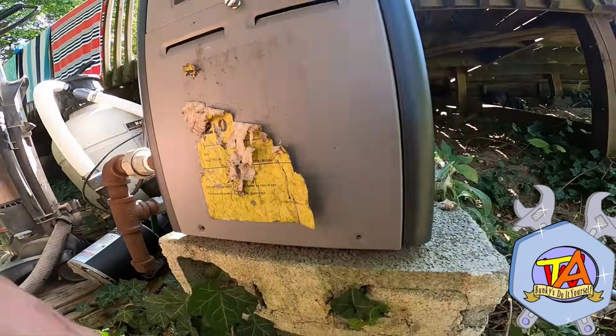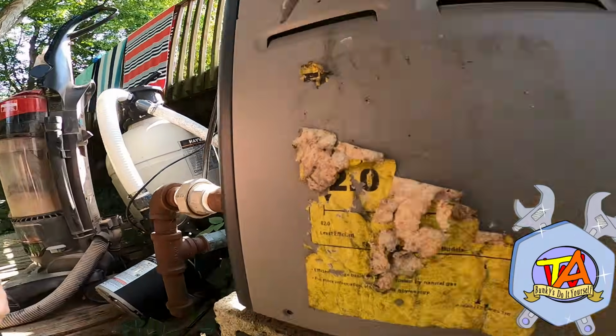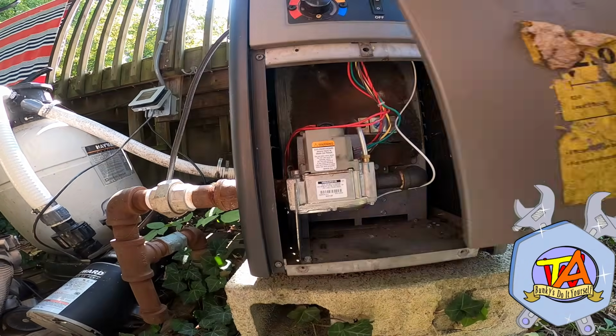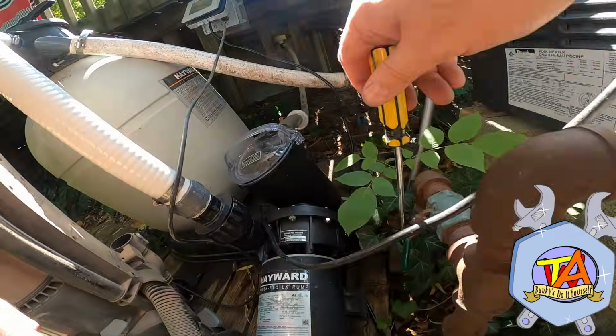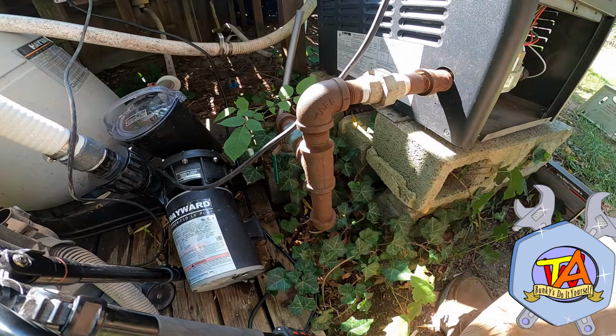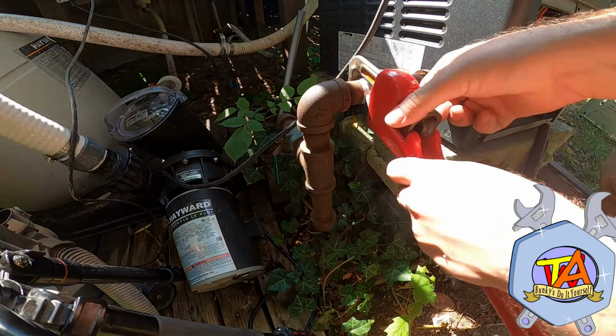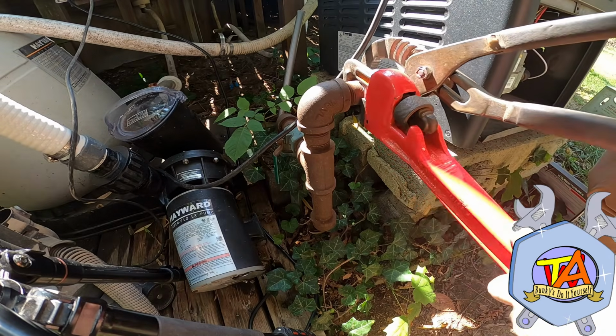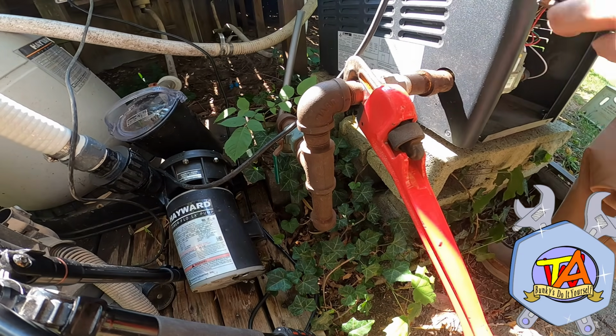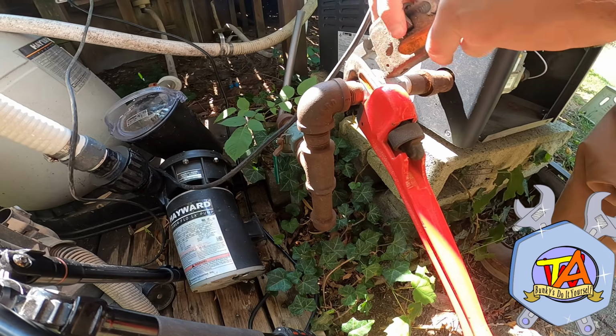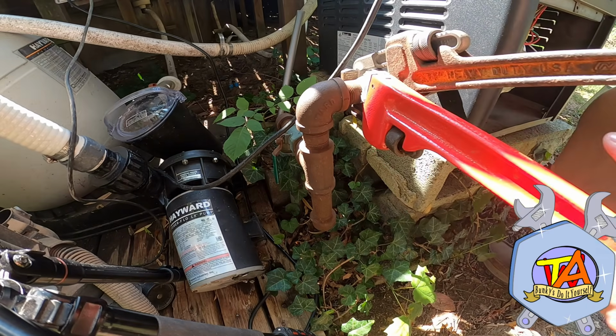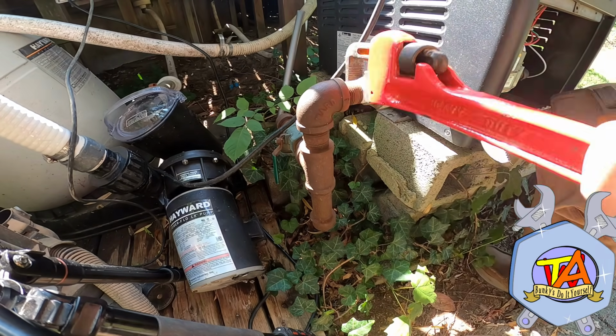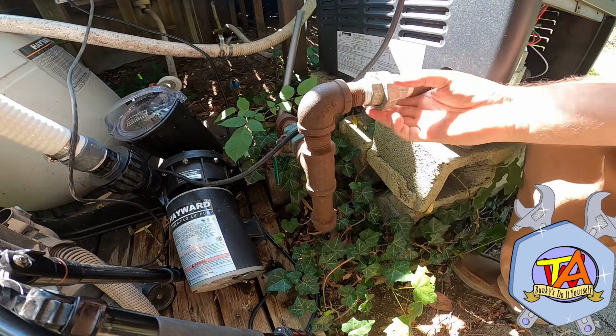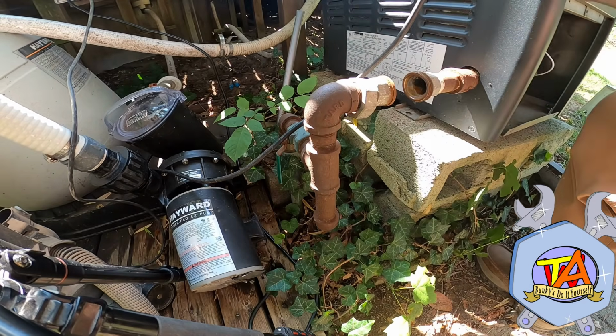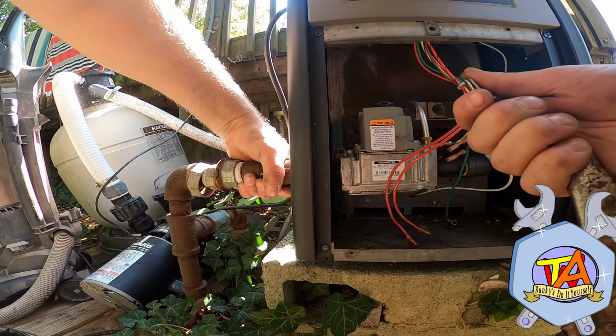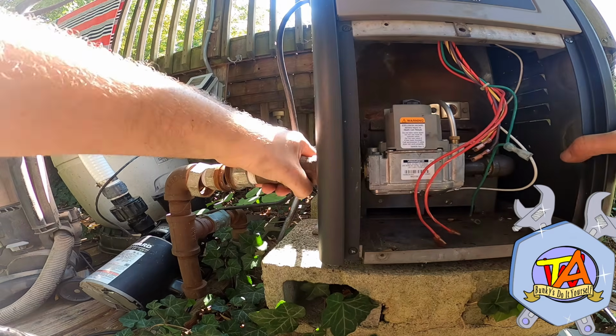I'm going to go ahead and end up removing the gas valve and the burner tray in order to suck out any debris that's fallen into the unit. Ensuring that all the gas valves are secure, I go ahead and start removing the pipes going into the unit. After detaching this union, I can unthread this pipe from the gas valve.